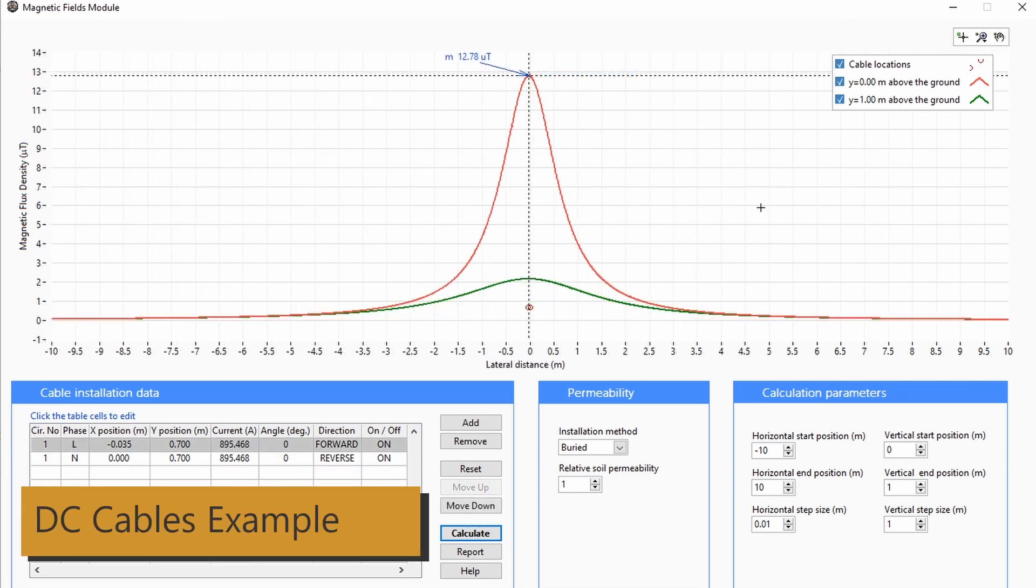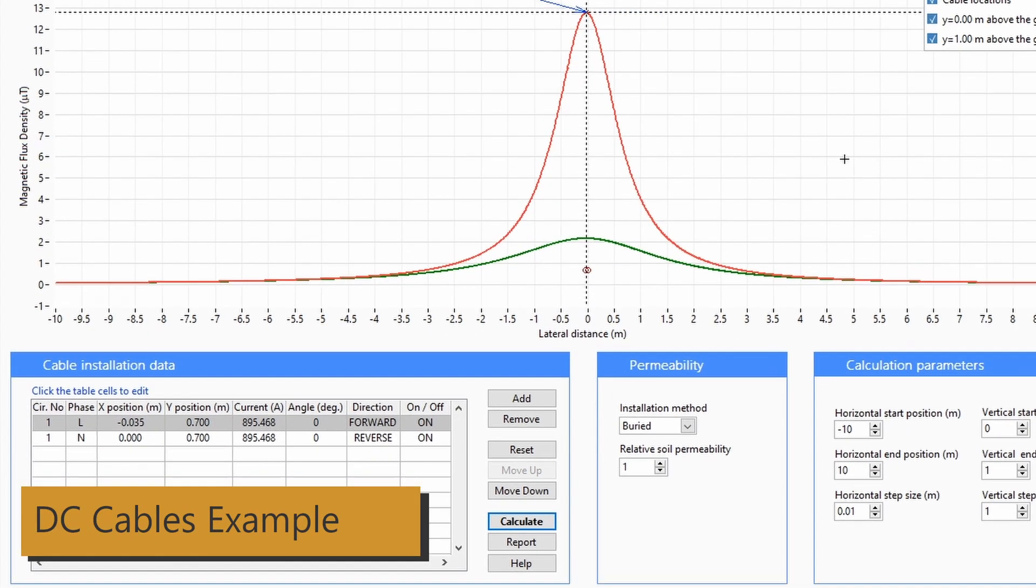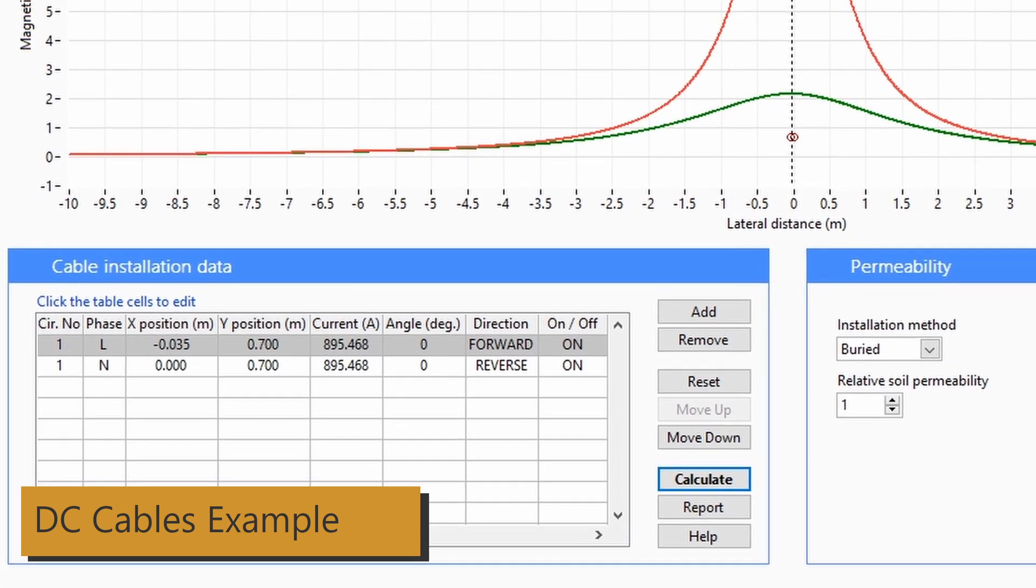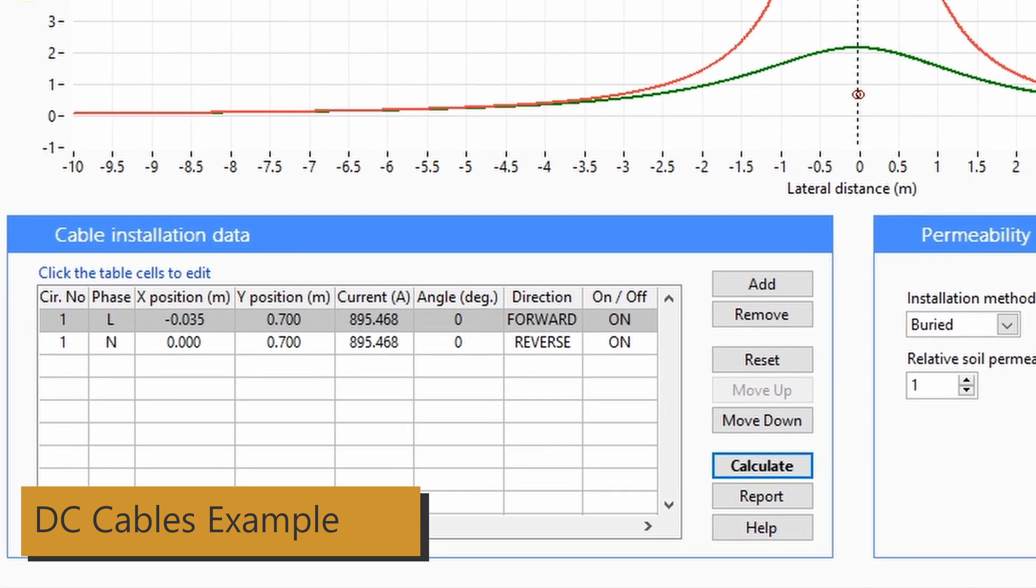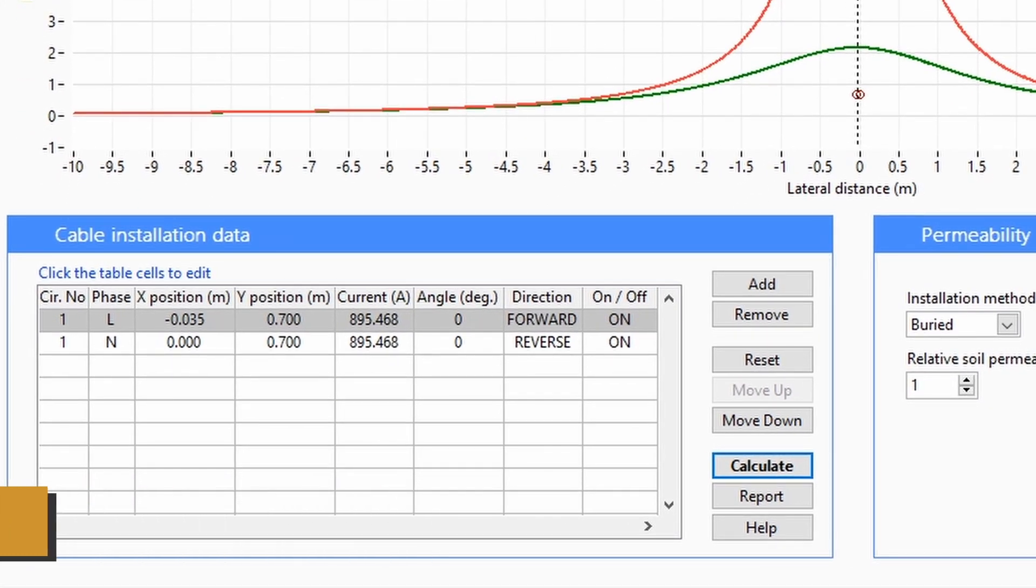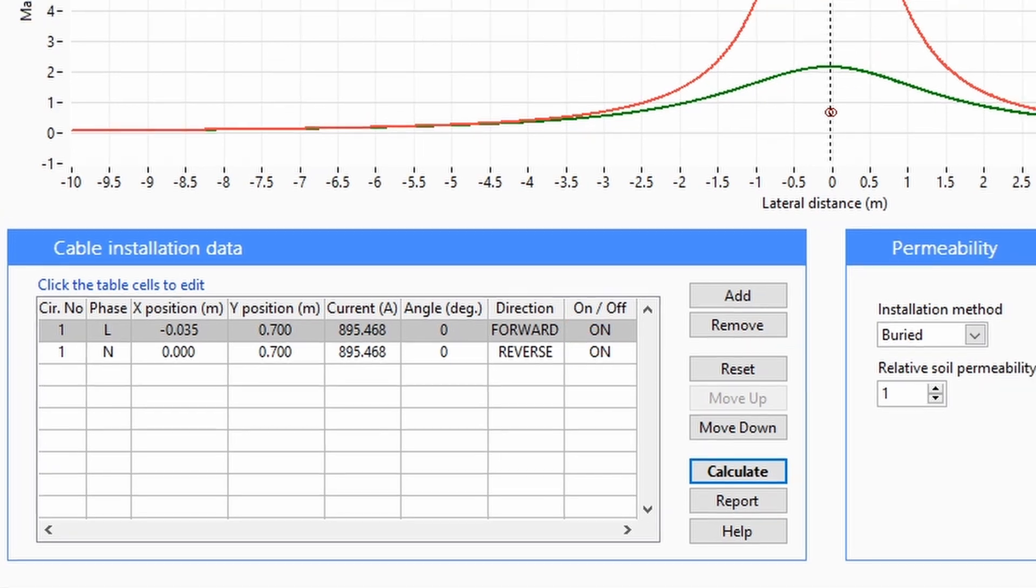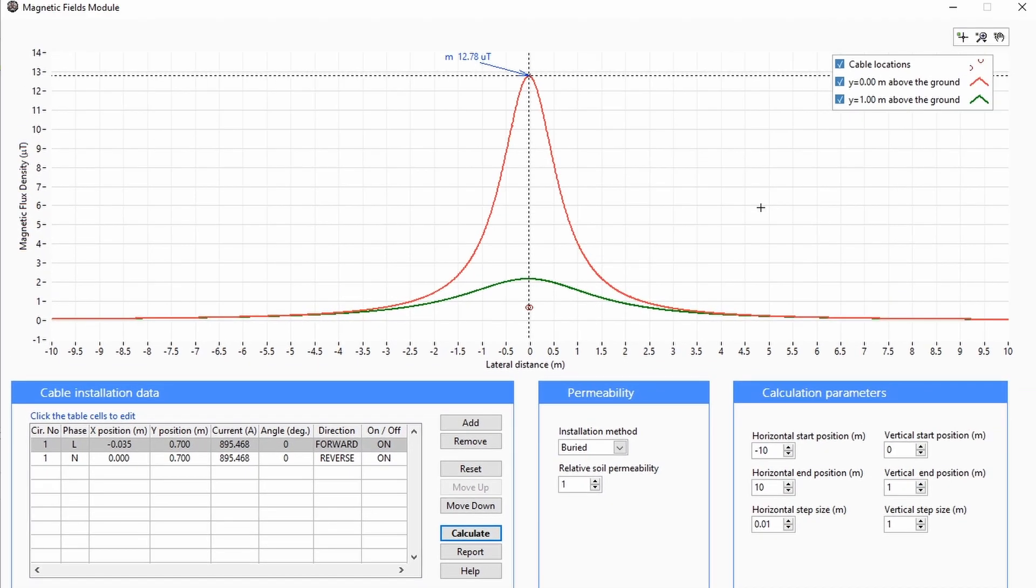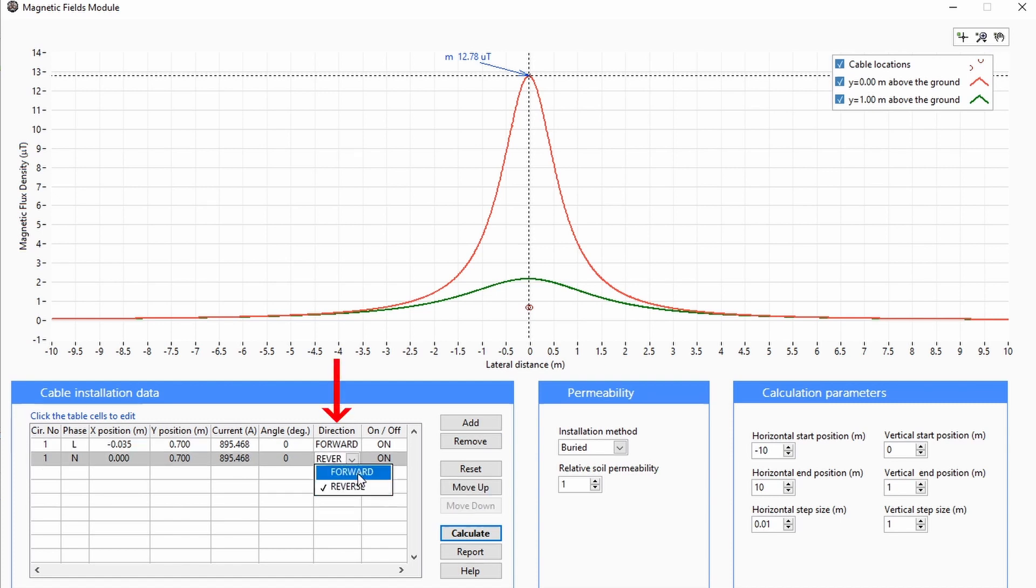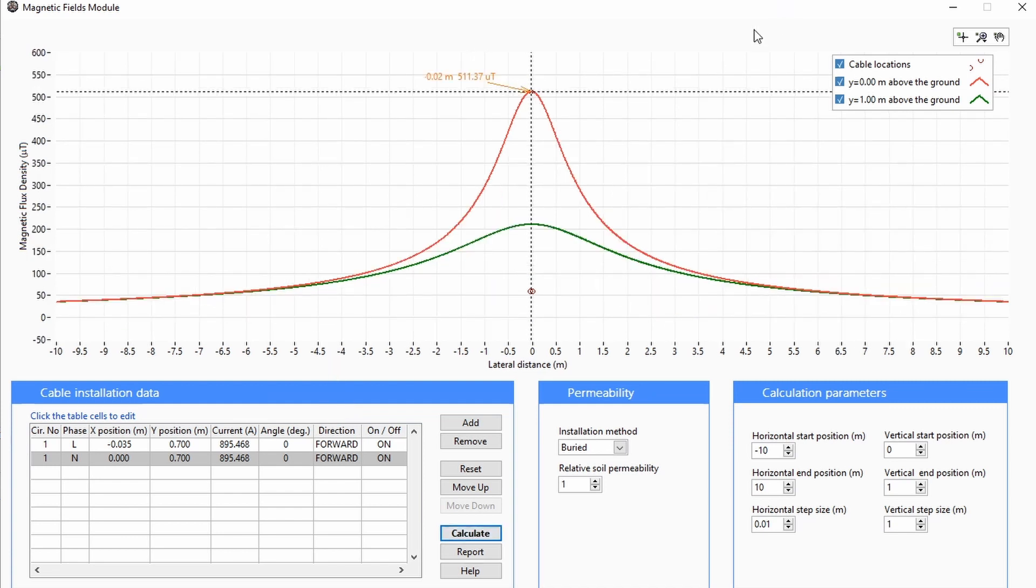Let's quickly take a look at DC cables. For DC cable systems, the static magnetic field around the positive and negative conductors will tend to cancel each other due to opposite directions of current flow. Just to demonstrate this canceling effect, we can change the direction of the current flow for both conductors to be the same. Subsequently, the magnetic field density is much higher.